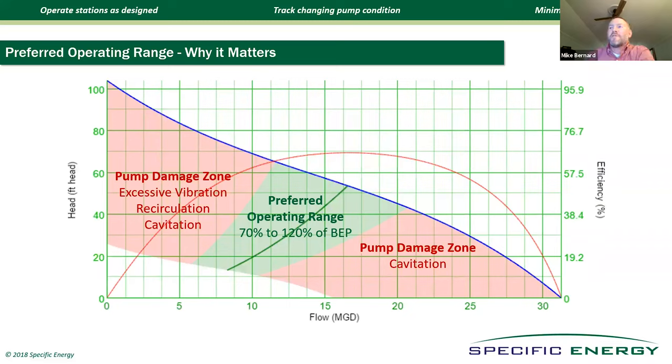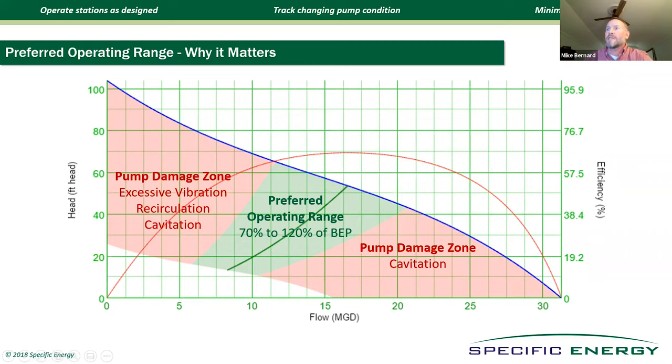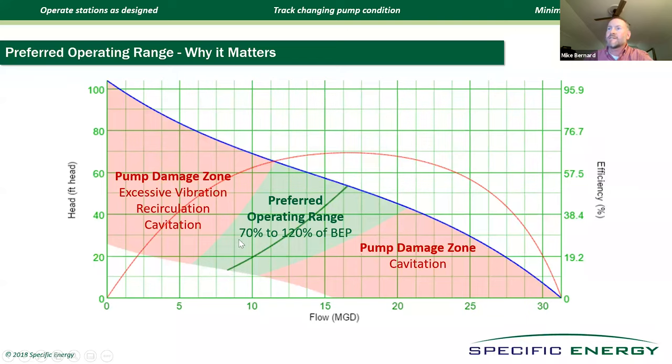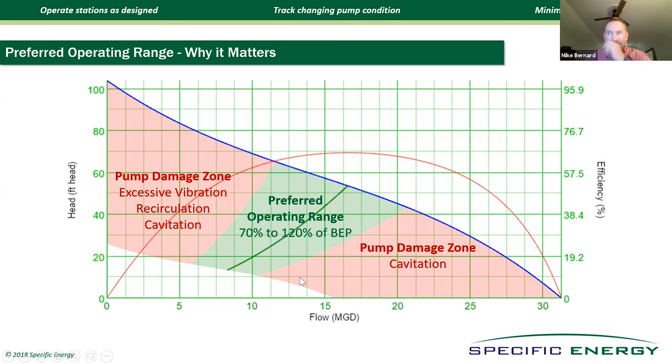We all know that about cars. We all understand how dashboards work, and we all know that we're not supposed to take our cars above the red line because fuel efficiency plummets, and engines don't last very long when you run them above the red line. Unfortunately, we understand this about cars, but very few people in the water and wastewater space have been properly trained to understand that every centrifugal pump also has red lines. As a matter of fact, they got two of them, one off the right and one off the left side of this very narrow range that we call the preferred operating range.